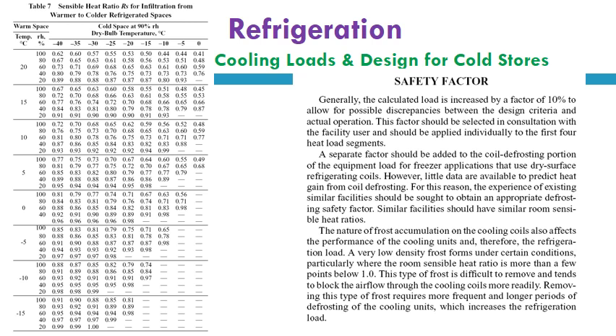Additional 10%. A separate factor should be added to the coil defrosting portion of the equipment load for freezer applications only that use dry surface refrigeration coils. However, little data are available to predict heat gain from coil defrosting. For this reason, the experience of existing similar facilities should be sought to obtain an appropriate defrost safety factor. Similar facilities should have similar room sensible heat ratios.